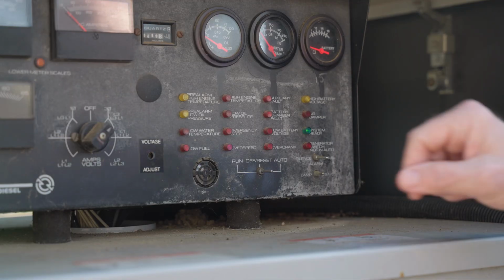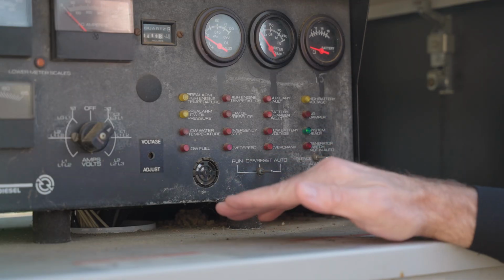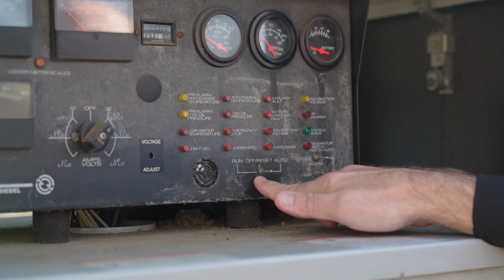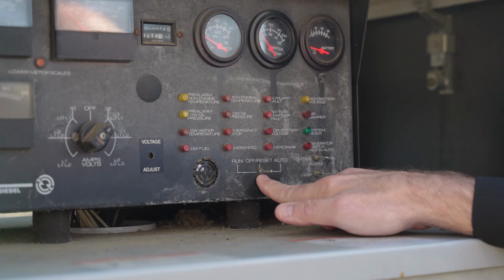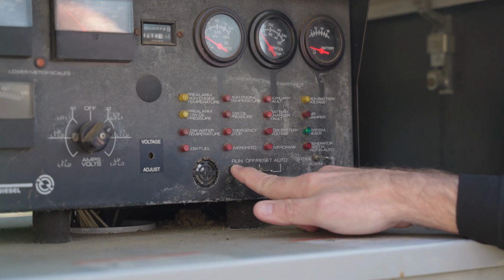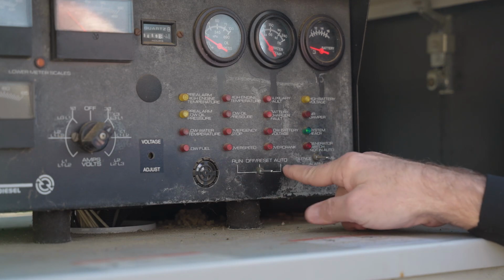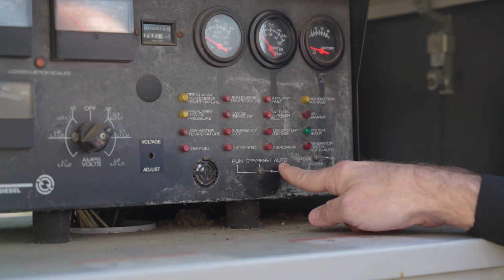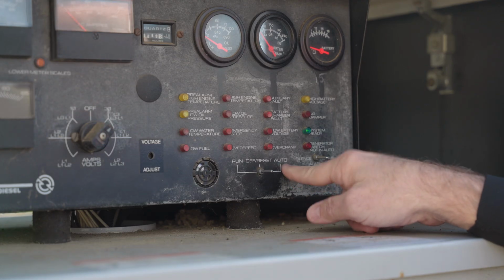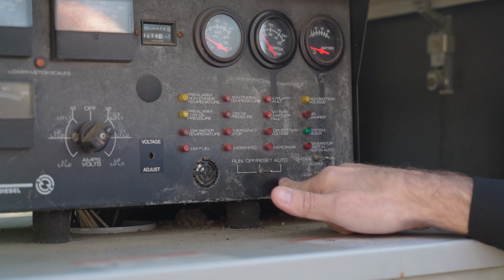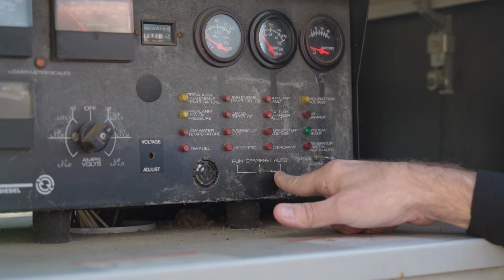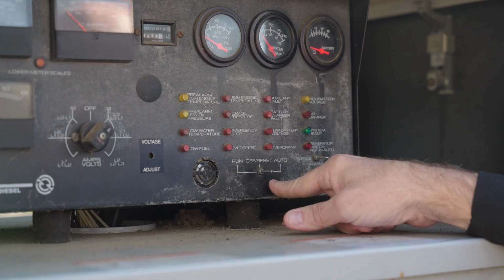So in our final thing that we're going to do before we start the generator, we want to look at the 3-position switch here, and we have 3 spots. We have run, we have off and reset, and we have auto. For the generator to start automatically in case of an outage, it always needs to be in the auto position. If it's not in the auto position, it will not start automatically.